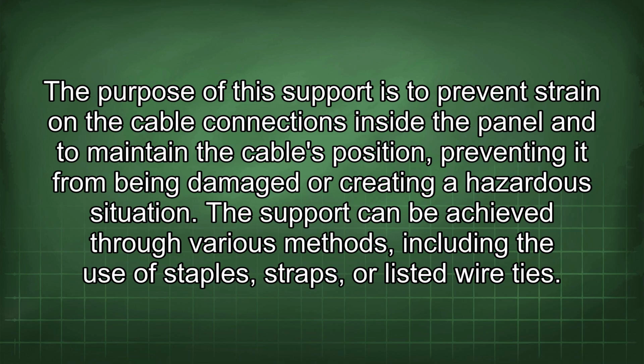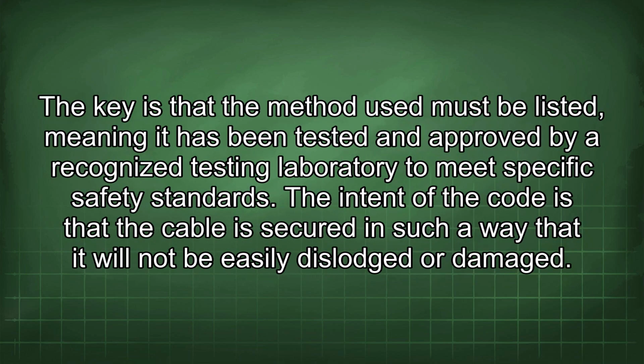The support can be achieved through various methods, including the use of staples, straps, or listed wire ties. The key is that the method used must be listed, meaning it has been tested and approved by a recognized testing laboratory to meet specific safety standards.